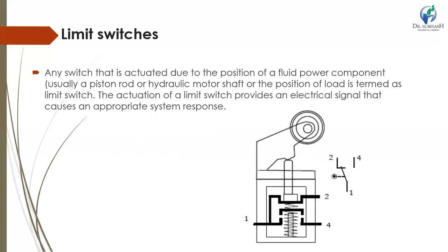Another one is the limit switch. Any switch that is actuated due to the position of a fluid power component, usually a piston rod or hydraulic motor shaft position or load, is termed a limit switch. The actuation of a limit switch provides an electrical signal so that the appropriate system can respond quickly. Limit switches perform the same function as push button switches. Push buttons are manually actuated whereas limit switches are mechanically actuated.